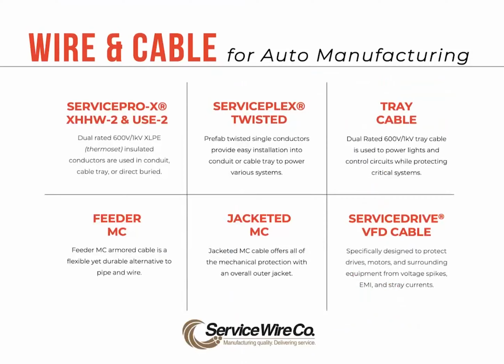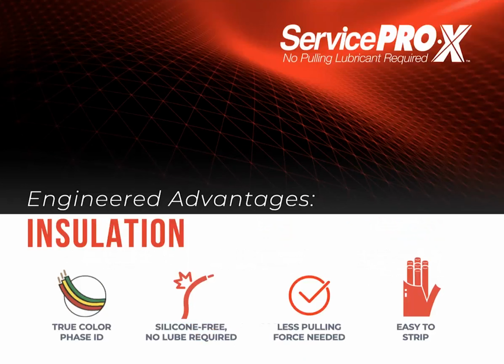Our most widely used products are silicone-free Service Pro X single conductors, ServicePlex twisted multi-conductor cable, dual-rated tray cable, UL type MC, and Service Drive VFD cable. Let's talk a little bit about why each of these products is preferred for this application. Service Wire's Service Pro X single conductors are available silicone-free to meet the installation requirements inside of an automotive manufacturing facility. Our singles can be used in conduit, cable tray, duct banks, or directly buried.